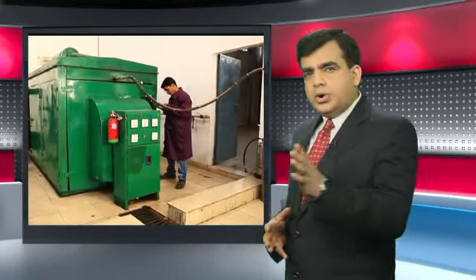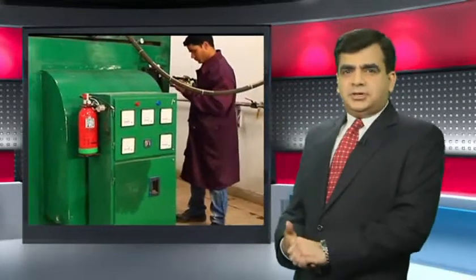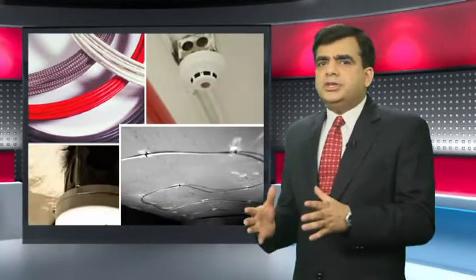Now, let's take a walk around the facility and see the generator protection system up close. Smoke detectors around the generator are designed to detect even the minutest particle of smoke and raise the alarm instantly. Detectors in this system include either smoke detectors, heat detectors and rate of rise detectors, LHS, heat sensing tube, or a combination of these. It can also feature a linear heat detection system. This audible alarm goes off as soon as the fire is detected, alerting personnel in the area to the danger.